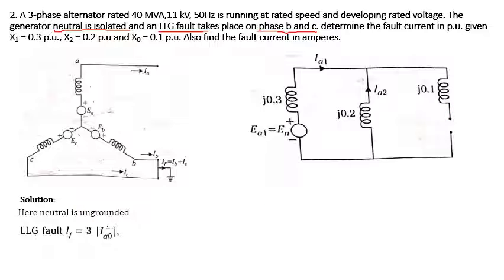So in actual operation we know that Z0 is equal to ZG0 plus 3Zn. So this consists of Z0 value, which is Zg0 plus 3Zn. But here, what happened? This is the 3Zn, the neutral is isolated, so we are not supposed to consider the value of Zn.